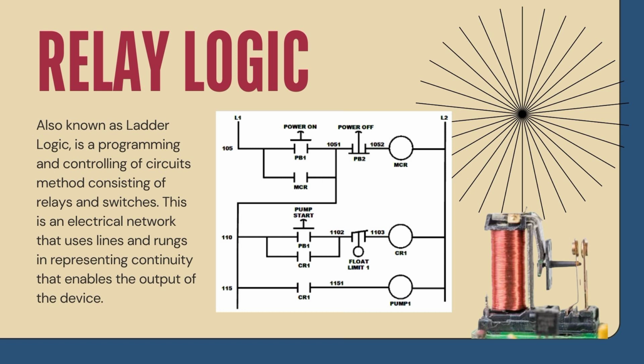Control devices are always between L1 and the outputs and can be connected in series or parallel. A device that executes stop is usually in series connection, while start functions are usually in parallel connection. Electrical devices are shown in their normal conditions.